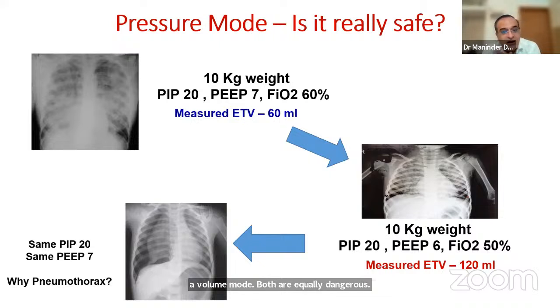We have to monitor the other variable — if you're using volume mode, the pressure varies; if you're using pressure mode, the volume varies. It's not that a PIP of 20 or 14 alone causes pneumothorax — the compliance determines whether the tidal volume is sufficient to cause a pneumothorax.